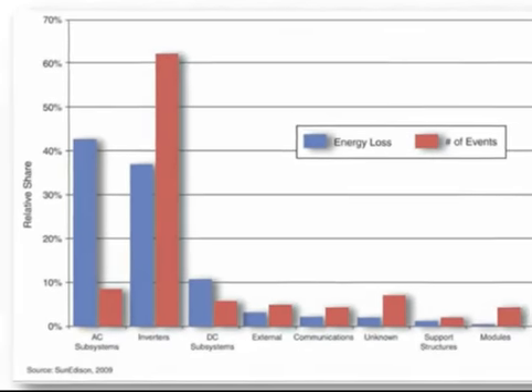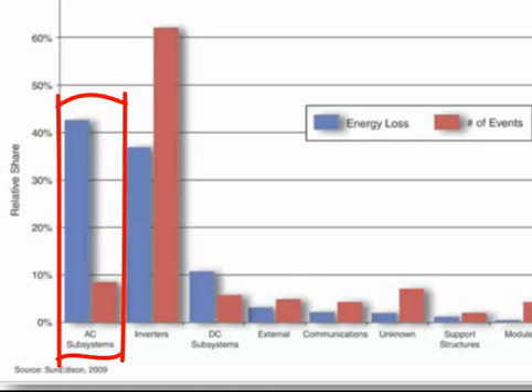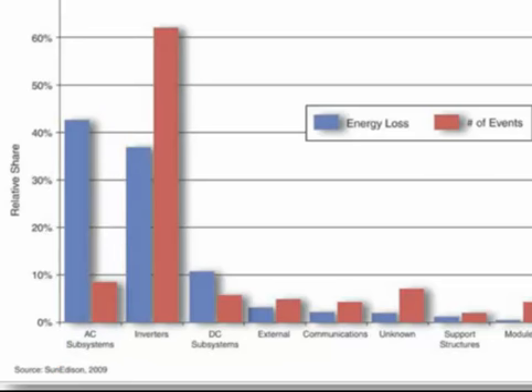In this first column, you can see AC subsystems. That's basically everything on the AC side of the inverter. Very expensive equipment because it's high voltage. We're talking about big transformers and switchgear. The occurrence of failure is relatively low, but they're going to be expensive because they're just expensive pieces of equipment.